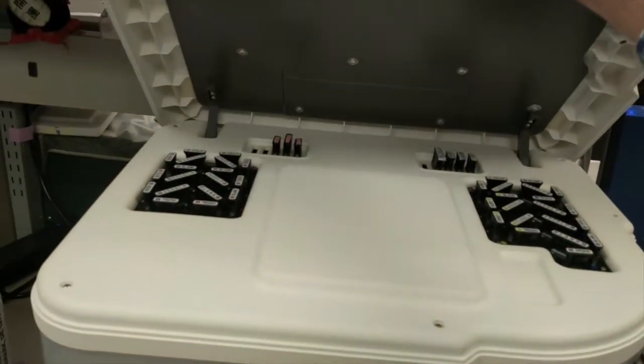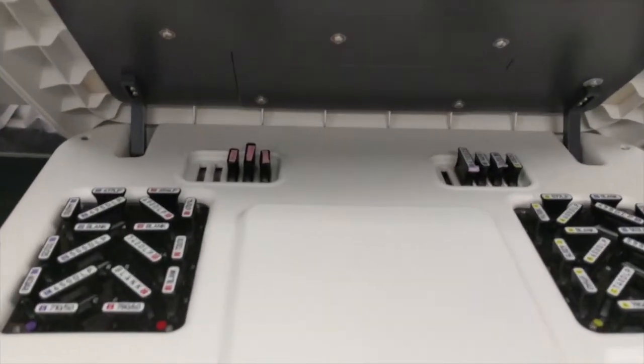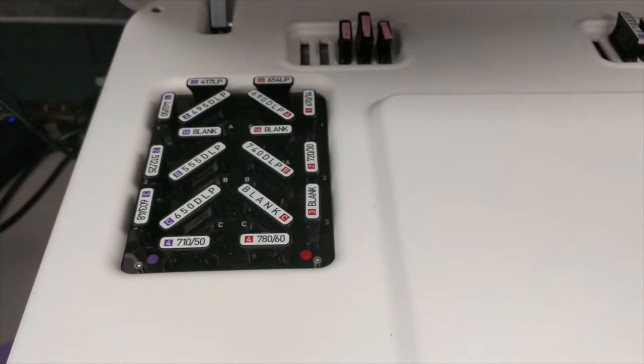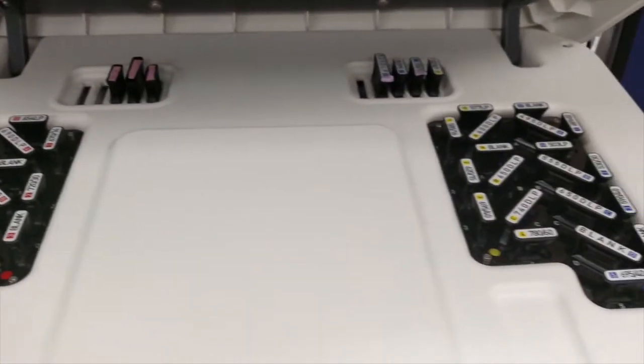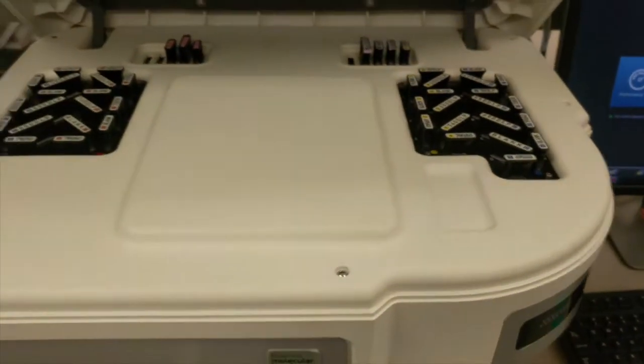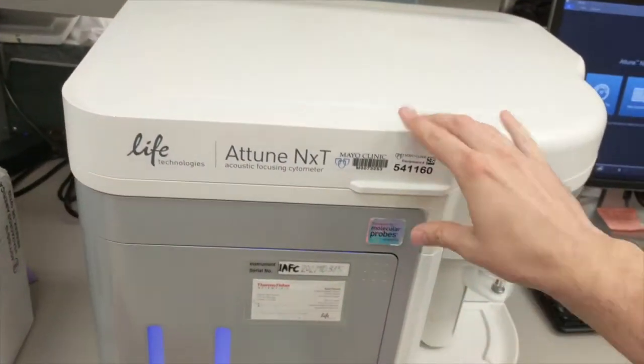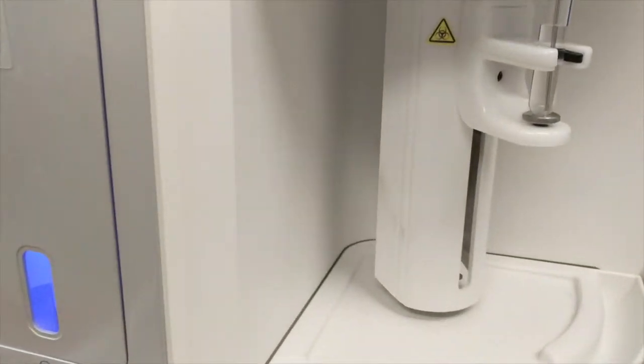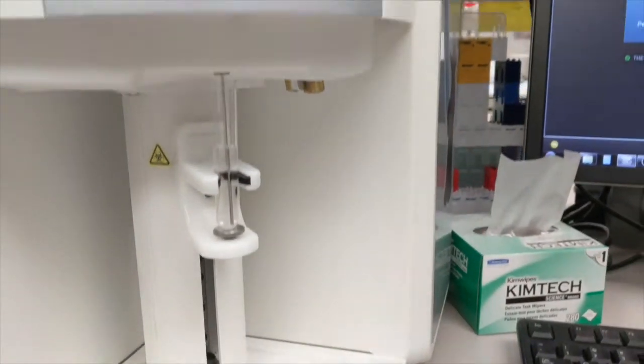If we open up the top of the Attune, you can see the filter set we use. Note that the filters and the detectors on the Attune follow a linear pattern rather than the octagon and trigon setups in the LSR. Also note that the Attune has four laser lines in a parallel configuration: violet, red, yellow, and blue. This configuration allows for many colors in a single panel. When we look at the sample intake, you can also see there is a sip, the metal piece that the liquid is taken up through, and a sample arm, which can be moved up and down.